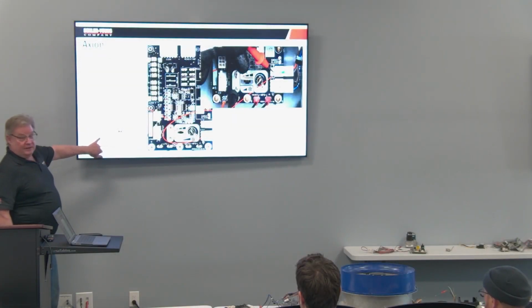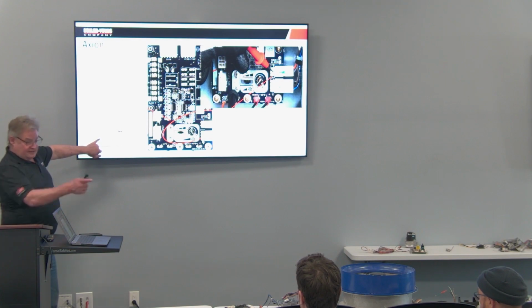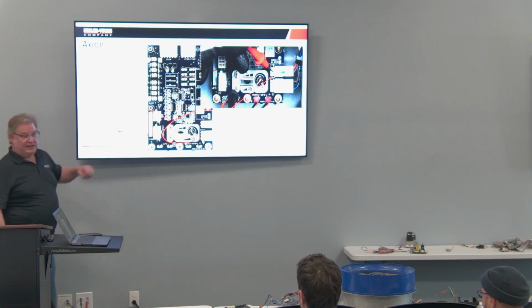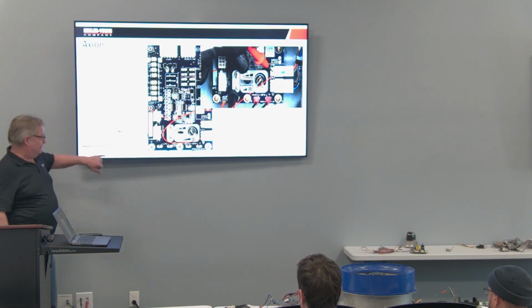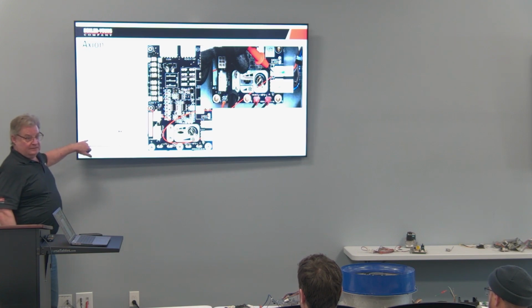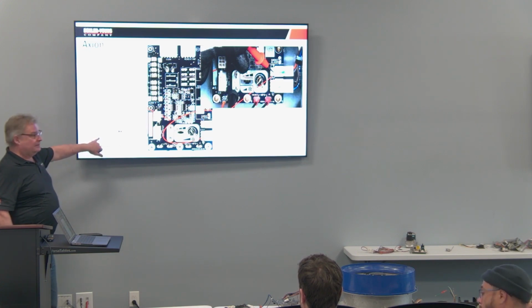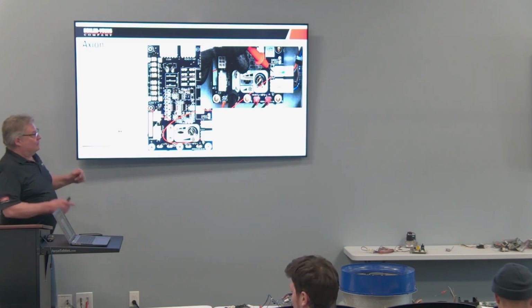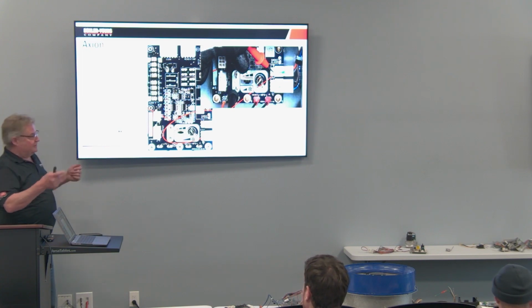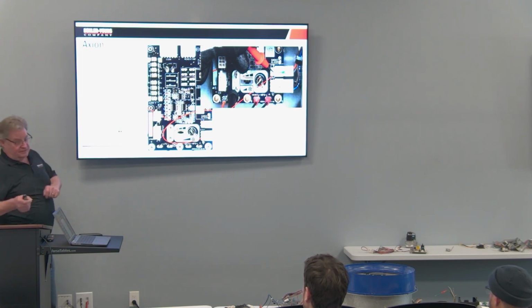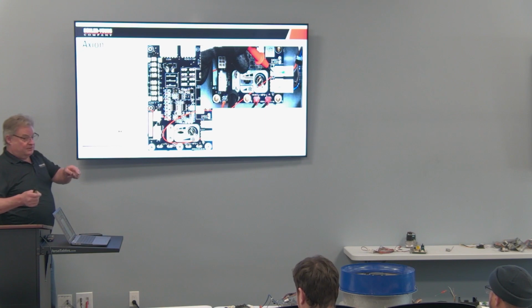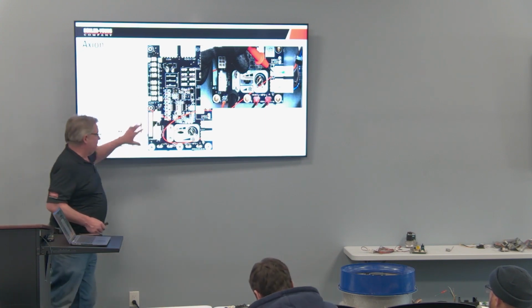So here's the logic that's on that board. An IFO here, and there's actually an IFO terminal that goes to the gas board. Those relays from the gas ignition board, indoor fan, that's what's coming into here. So again, 10 volts DC, orange, all the time. On a call, I should have voltage on the gray. If I do, the motor should be running. If I don't, that means either this has failed or this has failed.